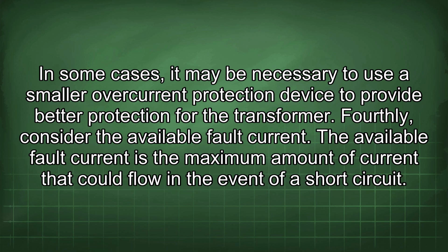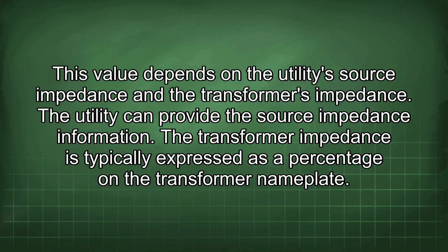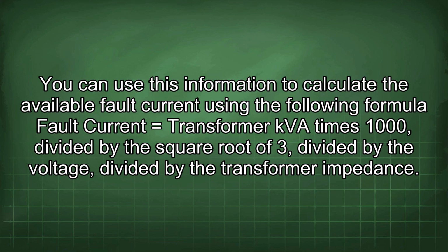The available fault current is the maximum amount of current that could flow in the event of a short circuit. This value depends on the utility source impedance and the transformer's impedance. The utility can provide the source impedance information. The transformer impedance is typically expressed as a percentage on the transformer nameplate. You can use this information to calculate the available fault current using the following formula: fault current equals transformer kVA times 1000 divided by the square root of 3 divided by the voltage divided by the transformer impedance.